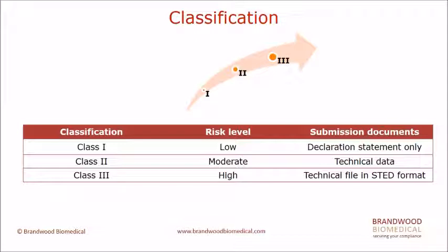We can see from the table here, for Class 1 devices, the submission document is purely the administrative documents, the declaration statements only. For Class 2, there are technical data required, such as the preclinical testing report and the QC testing report. For Class 3 devices, the full technical file in the STED format will be required as part of the pre-market submissions. So the higher the risk, the more documents are required as a part of the initial submissions.